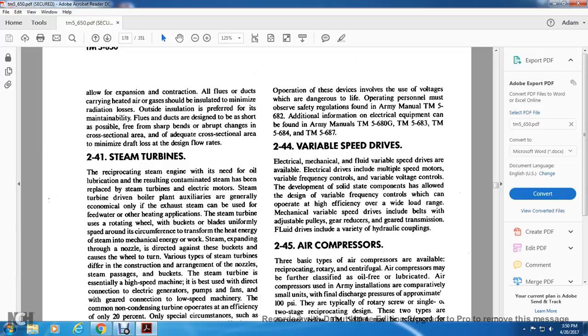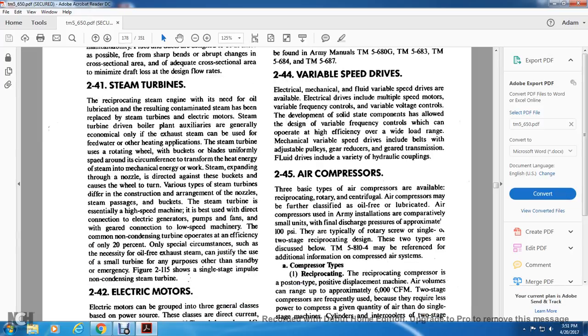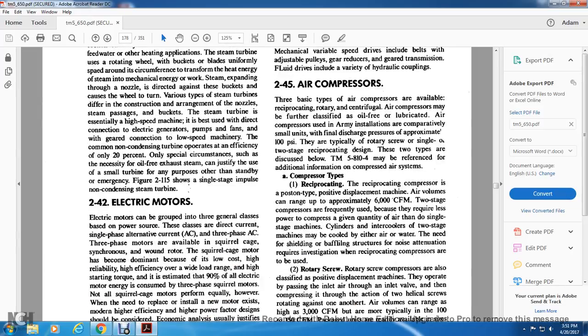2-44 Variable speed drives. Electrical, mechanical, and fluid variable speed drives are available. Available electrical drives include multiple-speed motors, variable frequency controls, and variable voltage controls. The development of solid-state components has also been applied to the variable frequency controls, which can be operated with high efficiency over a wide load range. Mechanical variable speed drives include belts, adjustable pulleys, gear reducers, transmissions, and fluid drives. Fluid drives include a variety of hydraulic couplings.